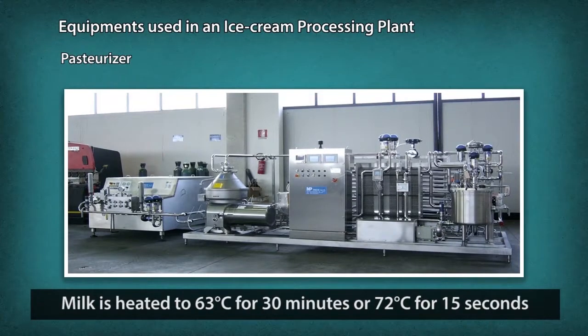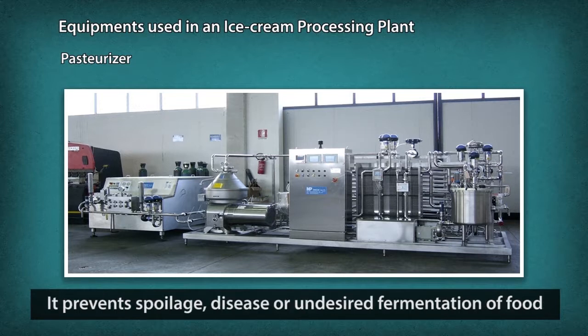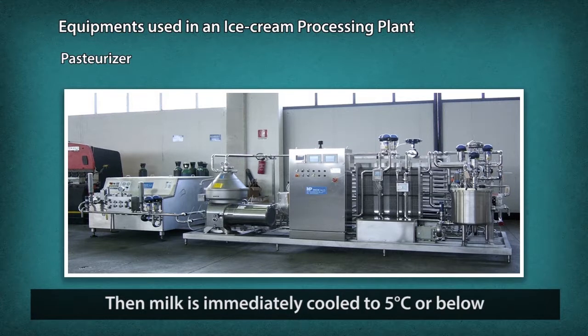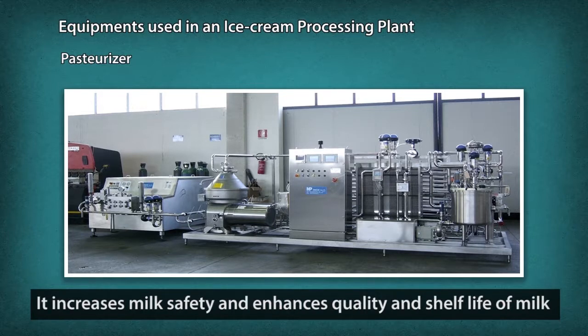Pasteurizer: Pasteurization of milk is the process of heating milk to 63 degrees centigrade for 30 minutes, or 72 degrees centigrade for 15 seconds, in order to kill microorganisms that could cause spoilage, disease or undesired fermentation of food. After pasteurization, the milk is immediately cooled to 5 degrees centigrade or below. The purpose of pasteurization is to increase milk safety for the consumers and to enhance the quality and shelf life of milk products.